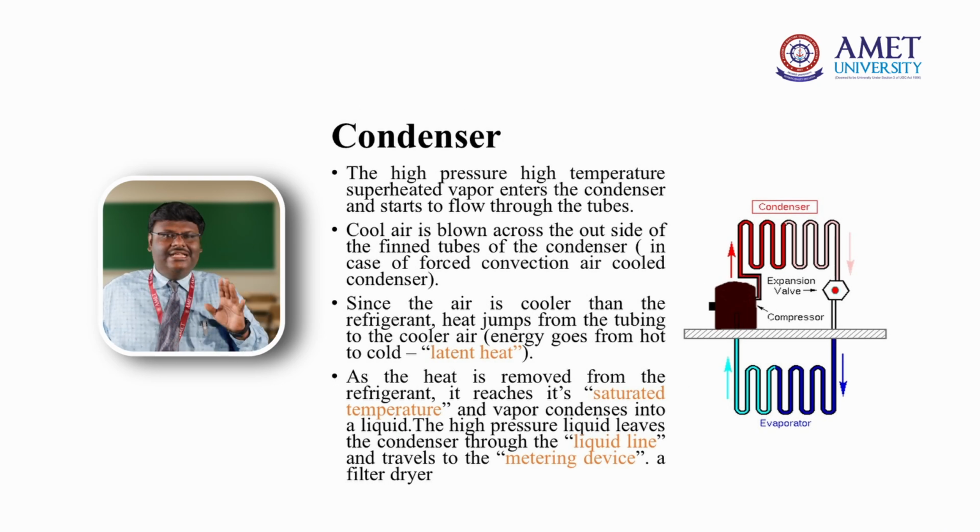In the condenser, as the name implies, condensation takes place. For condensing, I need a cooling medium. The cooling medium can be air, as in the air-cooled condensers present at the back of fridges, where you can see a natural convection air-cooled condenser which does not have any fan. Or else the condensers of split type air conditioning systems, where you see a fan for forcing air. So you need a cooling medium to condense the refrigerant. If the cooling medium is air, it is an air-cooled condenser. If the cooling medium is water, as employed in a ship, that is a shell and tube water cooled condenser.